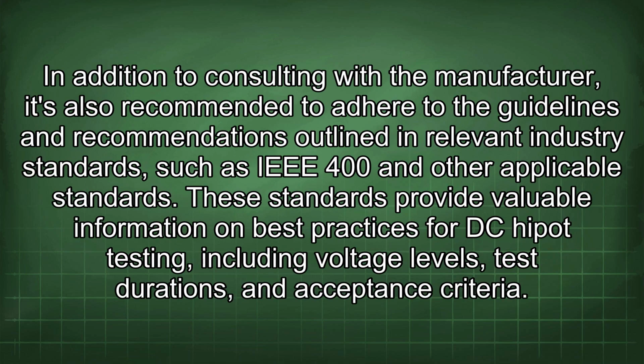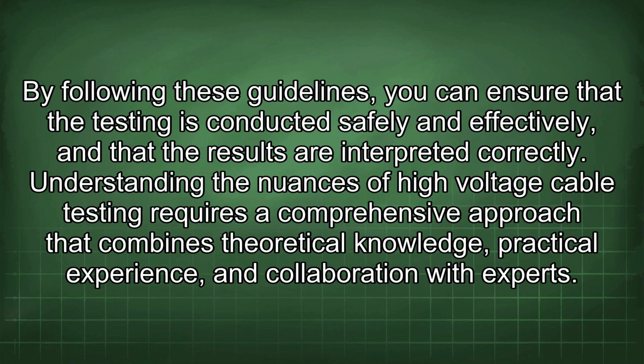In addition to consulting with the manufacturer, it's also recommended to adhere to the guidelines and recommendations outlined in relevant industry standards such as IEEE 400 and other applicable standards. These standards provide valuable information on best practices for DC hipot testing, including voltage levels, test durations, and acceptance criteria. By following these guidelines, you can ensure that the testing is conducted safely and effectively, and that the results are interpreted correctly. Understanding the nuances of high-voltage cable testing requires a comprehensive approach that combines theoretical knowledge, practical experience, and collaboration with experts.